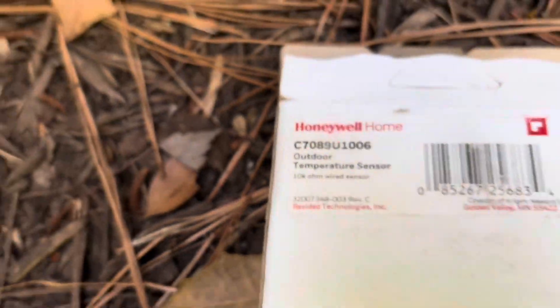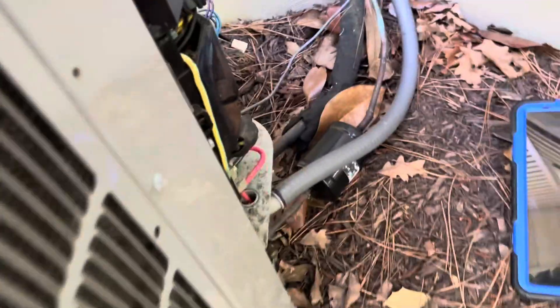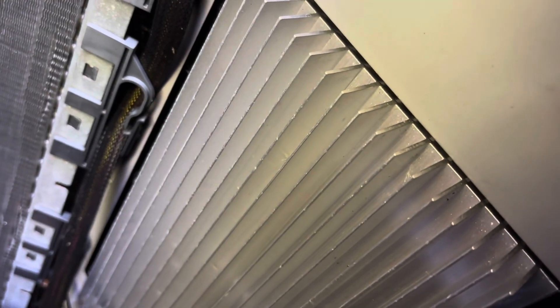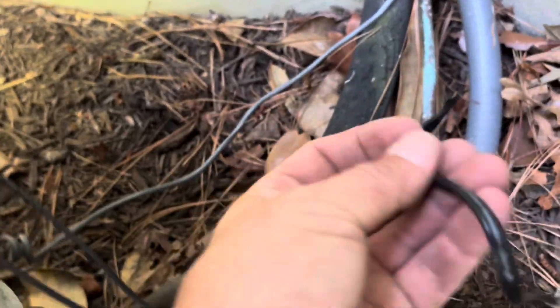I've got a Honeywell 10K sensor on my truck. We're going to try to use this to get the customer by and see if we can get this thing started with this sensor - we're going to go ahead and install it now. We'll probably have to use the same plug, so we'll have to splice it in. We got the 10K sensor mounted to the suction line there.